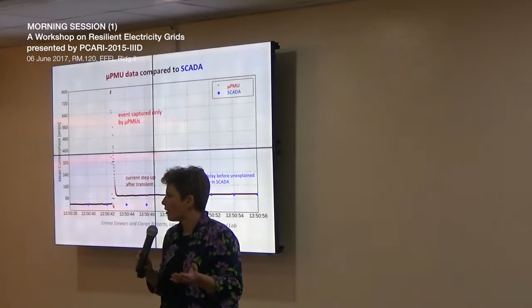And it could be a high impedance fault that is drawing just enough current to make this big spike, but not enough to actually trip a protective device. And usually that wouldn't actually hurt anything, except as a distribution operator, you would kind of like to know that this is going on. Also, if you're doing planning and any kind of engineering, you kind of want to know that these current spikes are happening.